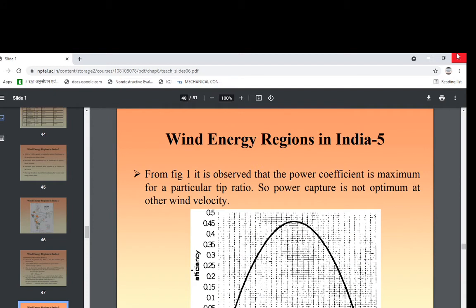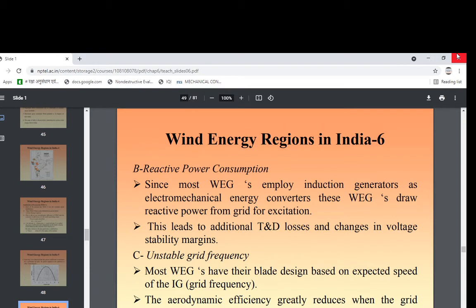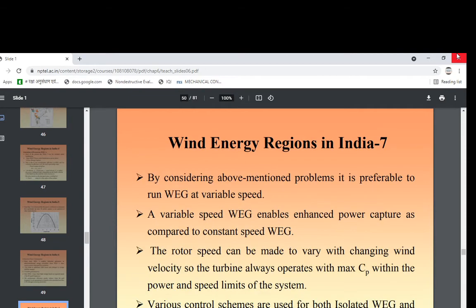The wind energy region in India. From figure 1, it is observed that the power coefficient is maximum for a particular tip speed ratio, so power capture is not optimum at other wind speeds. B. Reactive power consumption. Since most WEGs employ induction generators, as electromechanical energy converters they draw reactive power from the grid for excitation. This leads to additional T&D losses and a change in voltage stability margin. C. Unstable grid frequency. Most WEGs have their blade design based on the expected speed of the IGs. The aerodynamic efficiency is greatly reduced when the grid frequency is not maintained constant at a specified level, due to the changes in the tip speed ratio.